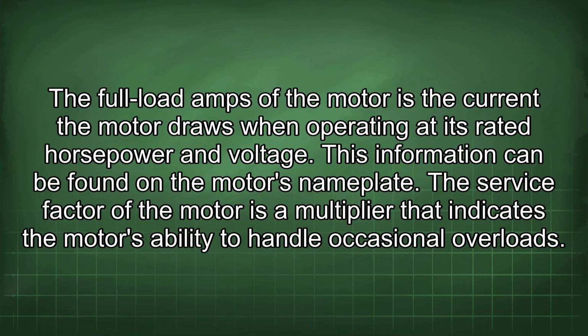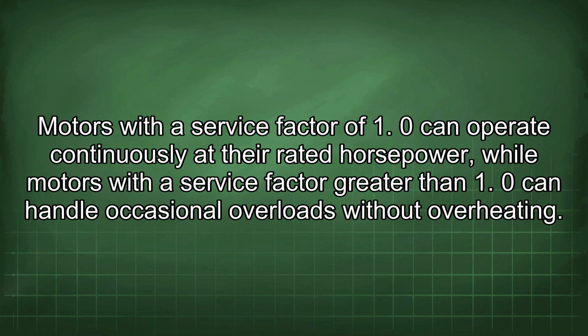The service factor of the motor is a multiplier that indicates the motor's ability to handle occasional overloads. Motors with a service factor of 1.0 can operate continuously at their rated horsepower, while motors with a service factor greater than 1.0 can handle occasional overloads without overheating.